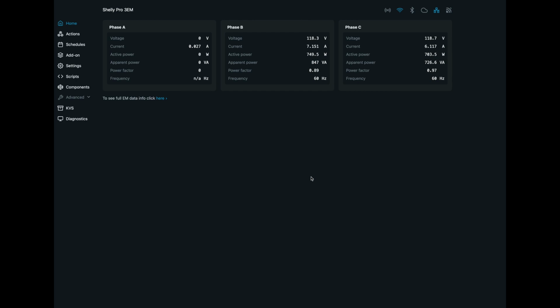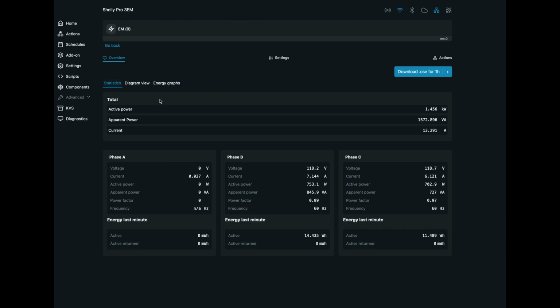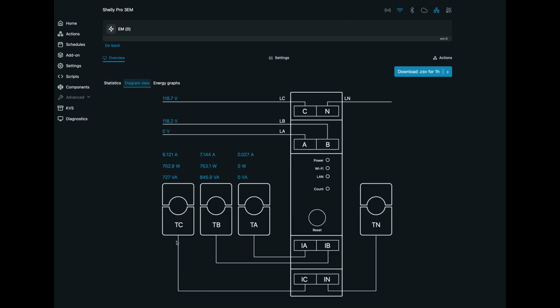If you're looking at energy monitoring, we're going to go to the desktop here and I'm going to check that out. On the Shelly Pro web interface, this is just by IP on my local network. I did use a LAN cable, Cat5, to connect and set my Wi-Fi up here. We have the three phases on the home screen. Phase A is obviously ABC, but phase C is the primary phase, and you can see that in the diagram view here. C is number one, B is number two, A is number three, and the C channel is also the power in for the device, and you need a neutral.